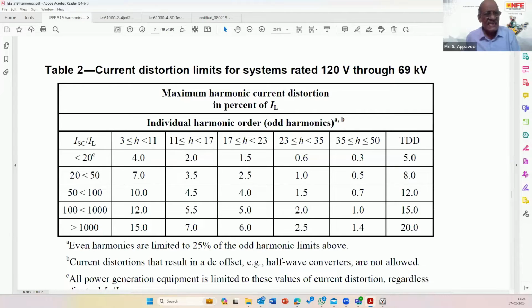There are certain situations the consumer can't control — for example, in the preceding one year or six months, a consumer might have had low consumption, or could have surrendered load due to marketing or production failures, other demand-driven issues, a pandemic, or educational institutions during lean periods. In such cases the IL could be less. If the IL is low for the same THD — say 10% THD — it will get escalated to a higher TDD. But if your IL is high, it will be reduced, say to 8%. So compliance also depends on the ISC.